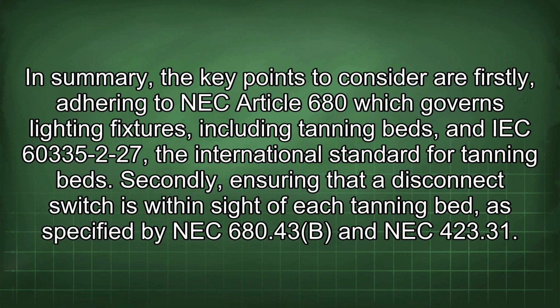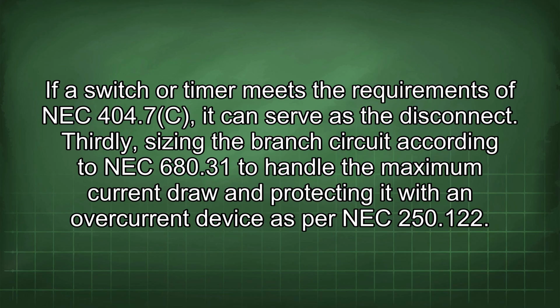In summary, the key points to consider are, firstly, adhering to NEC Article 680, which governs lighting fixtures, including tanning beds, and IEC 60335-2-27, the international standard for tanning beds. Secondly, ensuring that a disconnect switch is within sight of each tanning bed, as specified by NEC 680.43b and NEC 423.31. If a switch or timer meets the requirements of NEC 404.7c, it can serve as the disconnect.